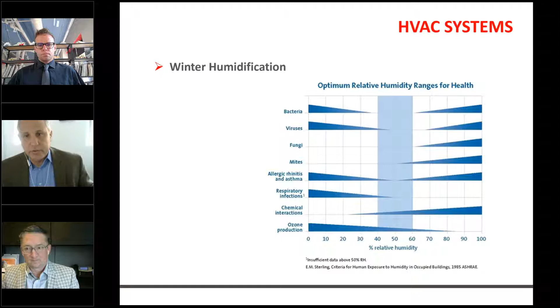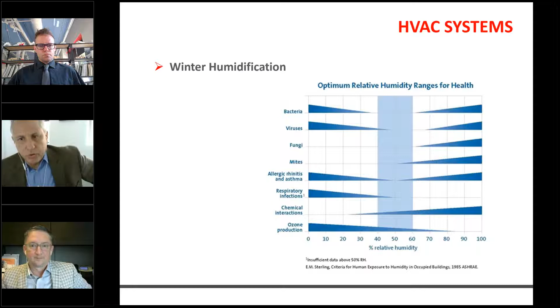There are some challenges—a fair amount of infrastructure is required: water lines, space in the air handler, steam, electricity, RO oftentimes, depending on the system installed, and stainless steel sections of ductwork and air handler to collect the moisture and drain it properly. As well as the building itself—most older buildings have potential for condensation on window frames that aren't thermally broken. So there are challenges in retrofits; it's best suited for new construction or newer buildings with good building envelope construction.